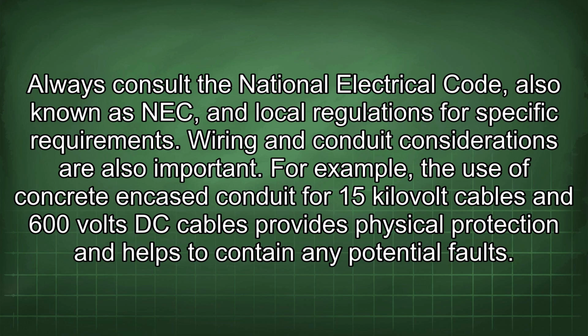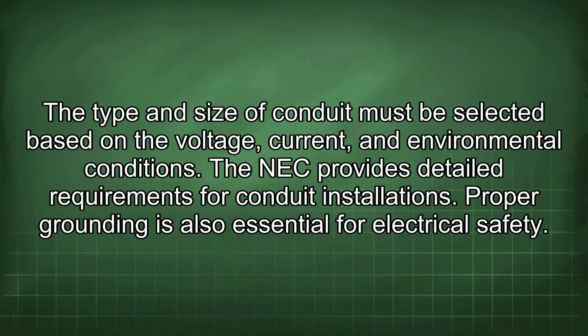For example, the use of concrete encased conduit for 15 kilovolt cables and 600 volts DC cables provides physical protection and helps to contain any potential faults. The type and size of conduit must be selected based on the voltage, current, and environmental conditions. The NEC provides detailed requirements for conduit installations.